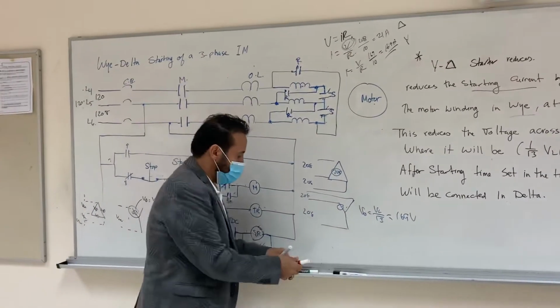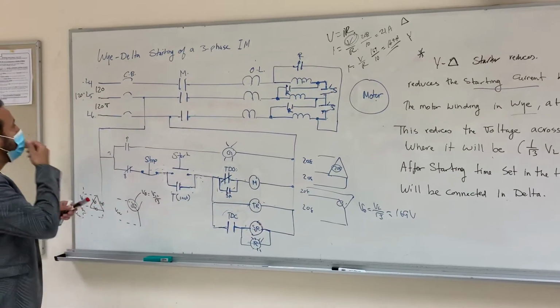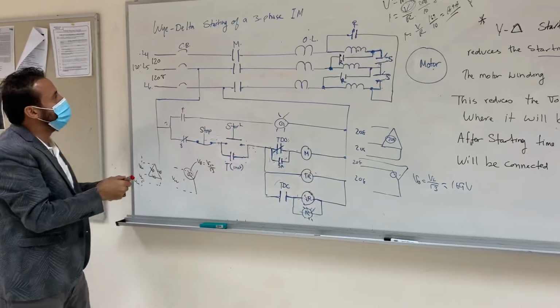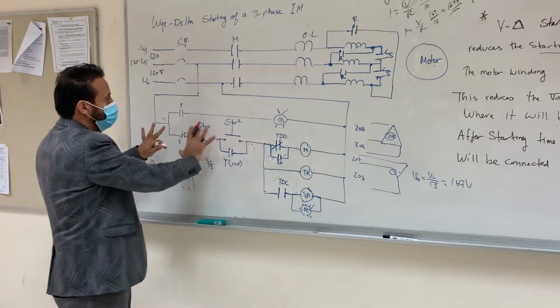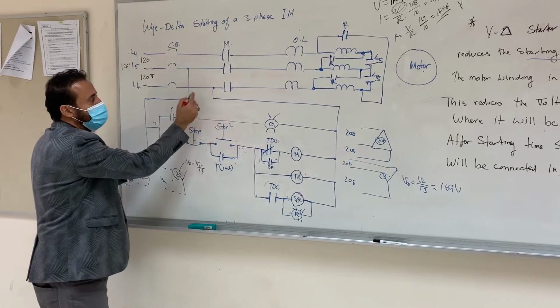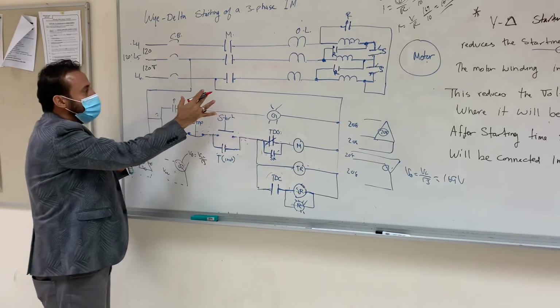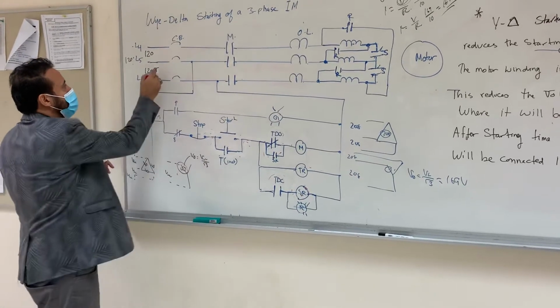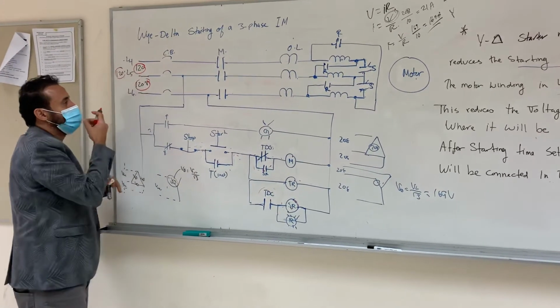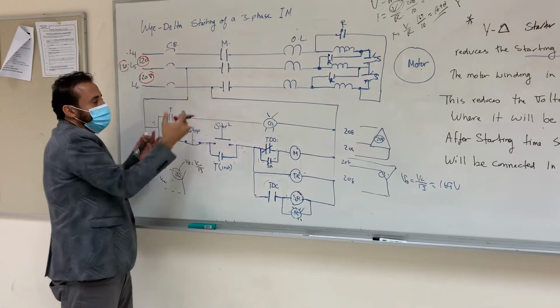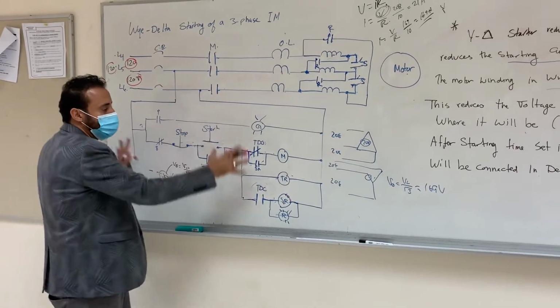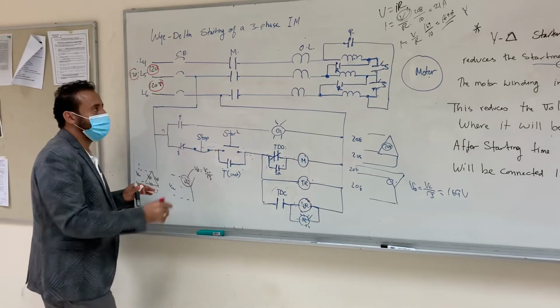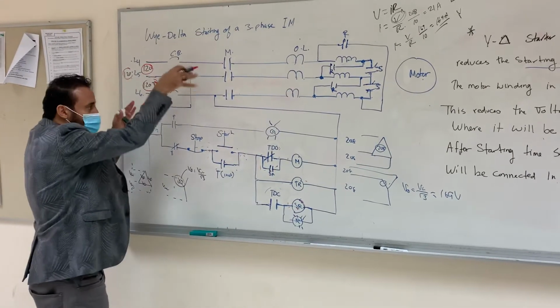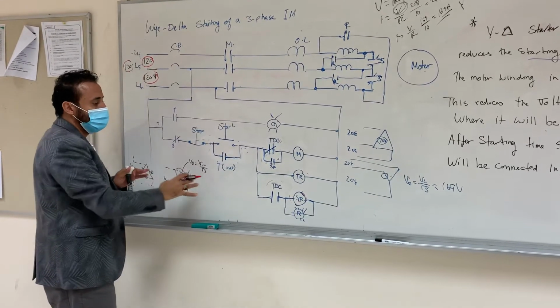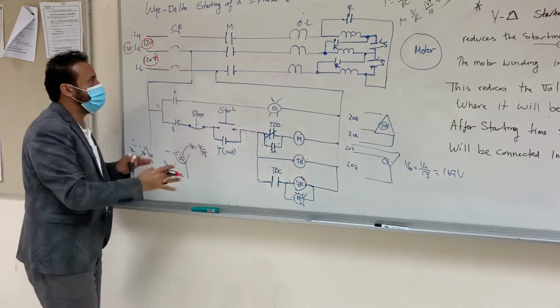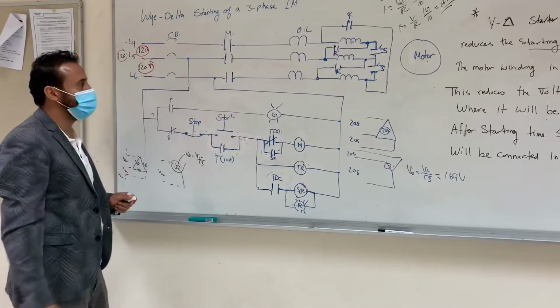I'm going to use those colors right here. Now, this is the source, 120. This is the control circuit. We notice that there is no transformer in this circuit because the source is 120. So the source 120 means we don't need to go down, because we know the control circuit works with 120 volts. Before we used to connect 208, so we bring 208 to 120, and now we don't need to use a transformer because the source initially is 120.